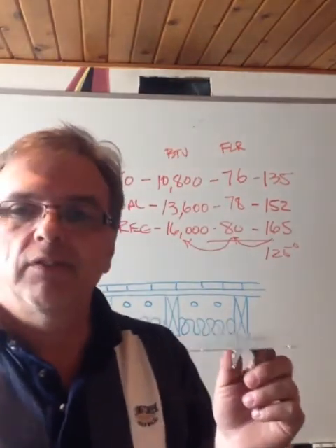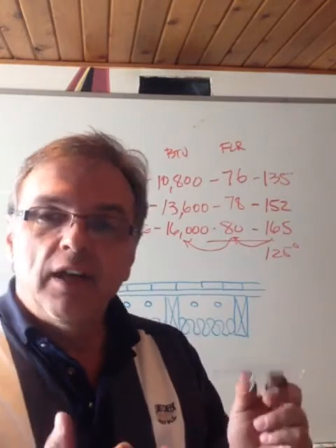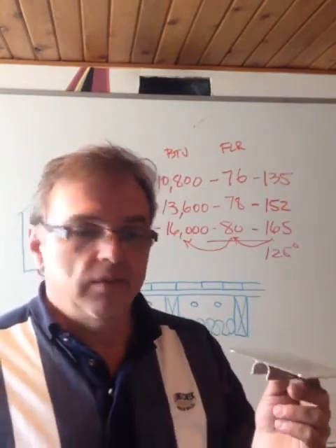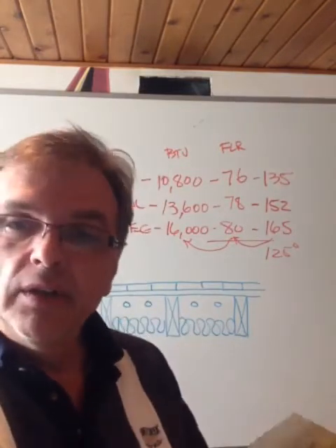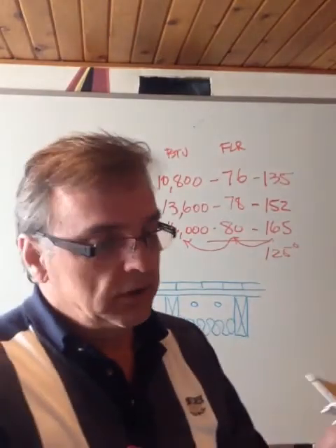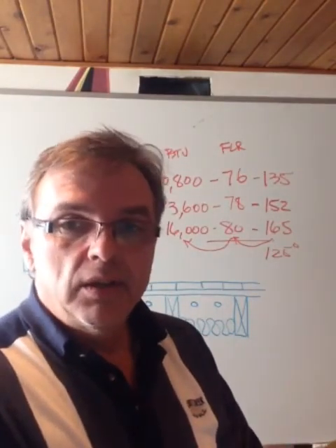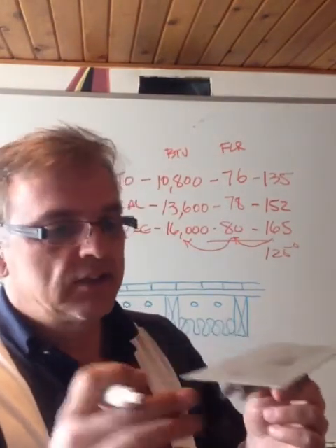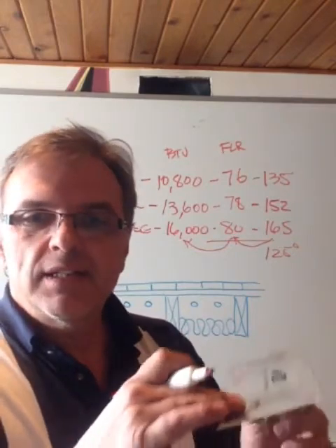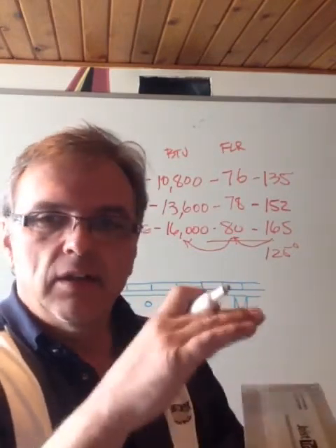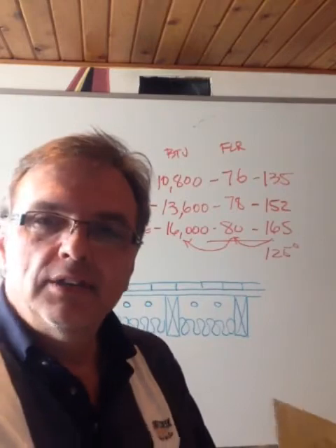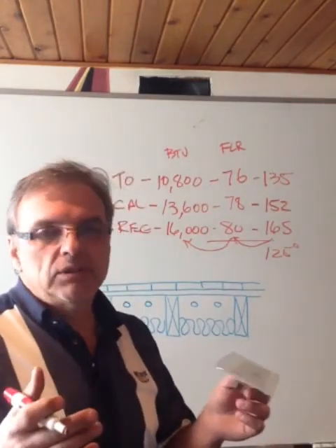So what you've effectively done, you've brought the conductiveness back into the equation. The fluid in the tubing conducts to the tubing, conducts to the heat transfer plate, the heat transfer plate spreads that heat across the floor, conducts it to the underside of the floor, allows you to do a much lower water temperature.